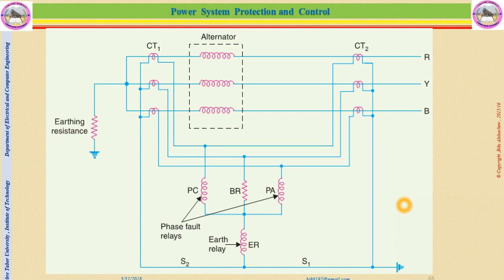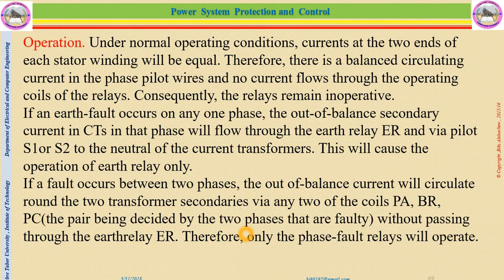This is the modified version of the previous one. Here you can see this is PA and PC. Those are phase fault relays. They will act only for phase faults. And this one is BR, balancing resistance. Remember, this is not a relay, this is a resistance. And this one is the earth relay, which will trip only for the earth fault. Let us see the operation in such manner.